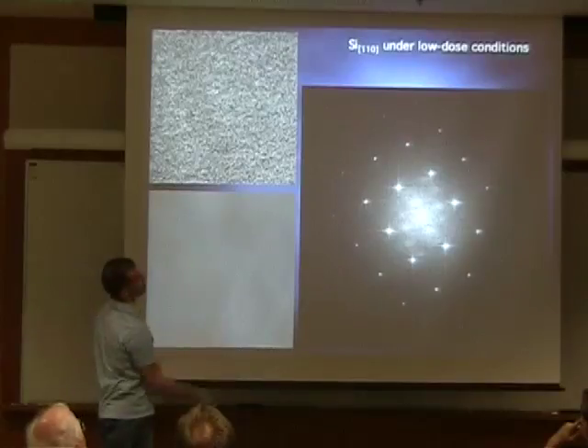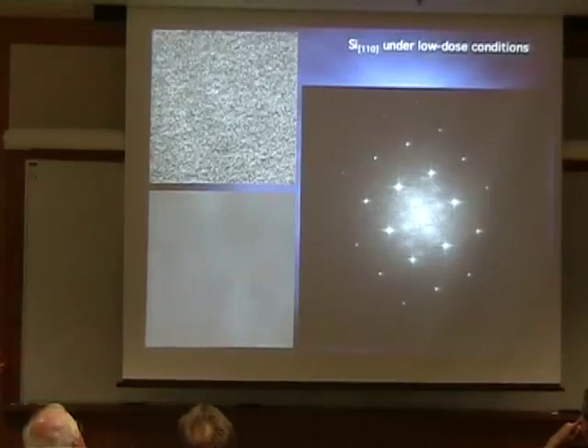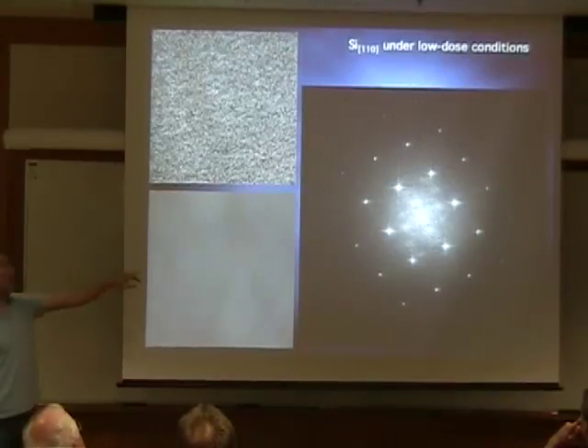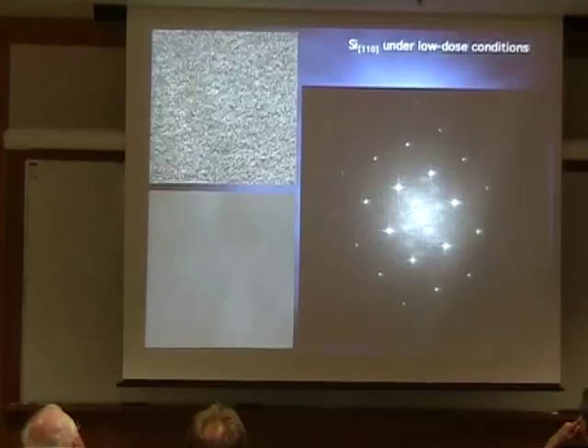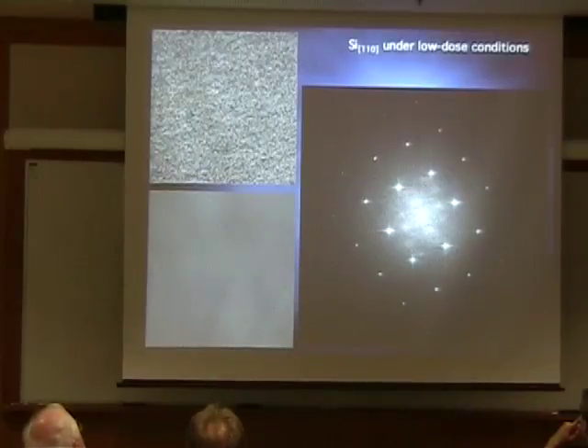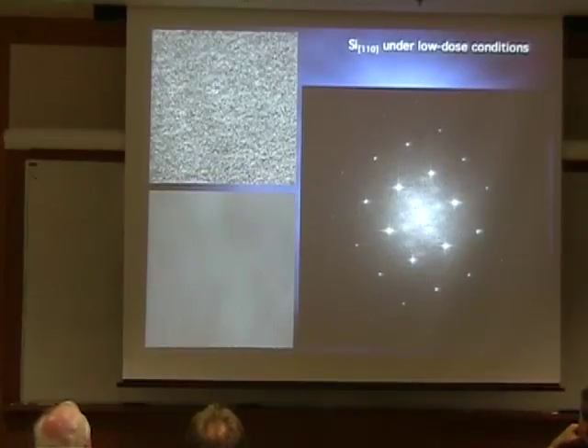The first thing we wanted to do was test a normal material science sample that they used for calibration — to get down to 0.8 angstrom resolution — to see how much information we would get using it the exact same way we would with biological samples. The furthest spot, which is also visible at the bottom, is 1 angstrom resolution — actually 1.02 angstroms. That shows us that although this is a heavy-atom silicon sample with a lot of amplitude contrast, the microscope under low-dose conditions can still record images out to at least 1 angstrom.